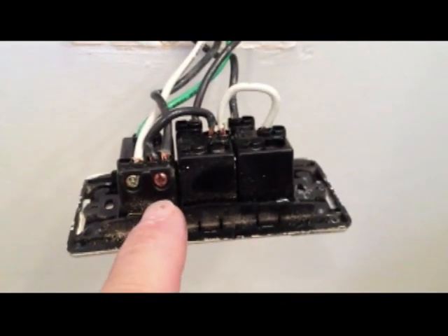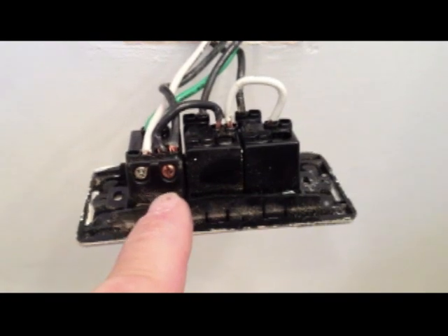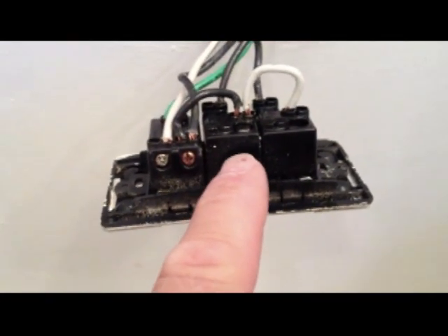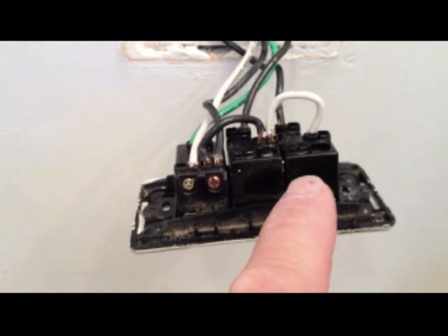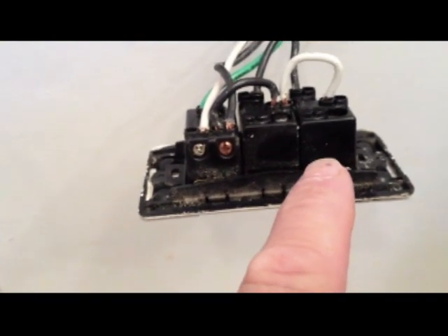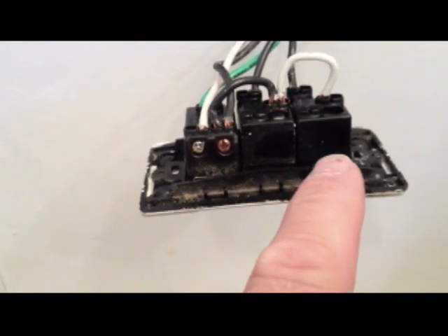Anyhow, I think I've found where the problem is. Right here is where the power comes into the switch, or into the receptacle I should say. Then they jumper it over for power to this switch. And here's where they did make a little bit of a mistake, is he used a white wire to jump it over to the second switch. But looking at this, you can tell that that should be a hot wire and it should have been black.